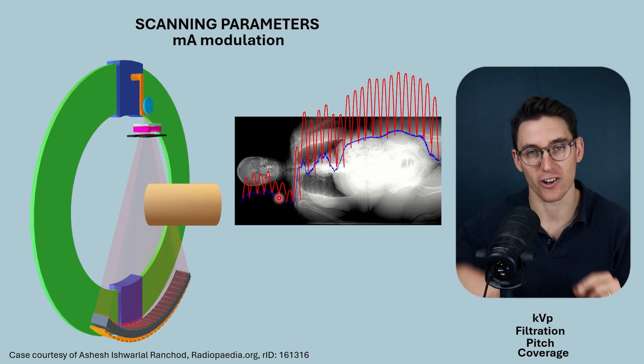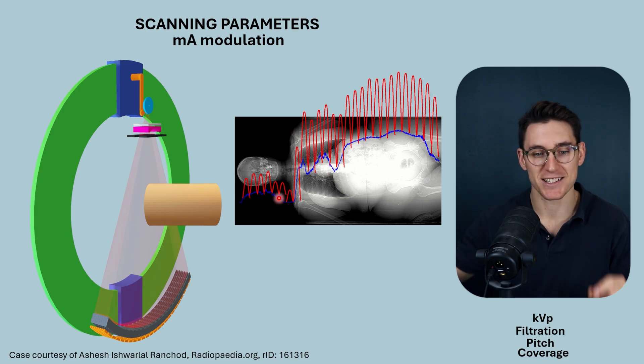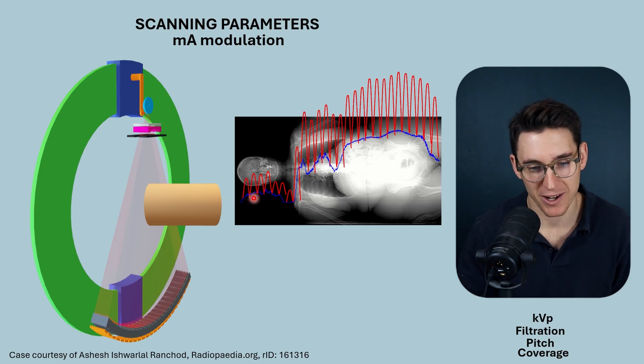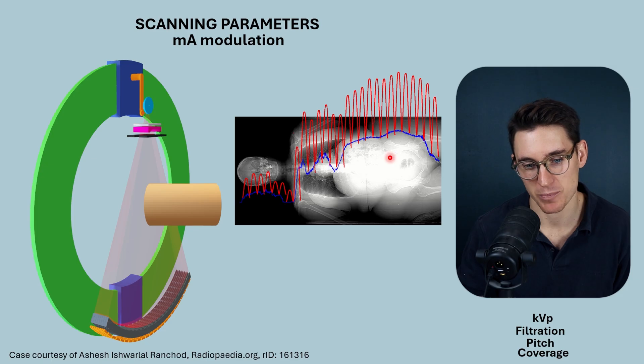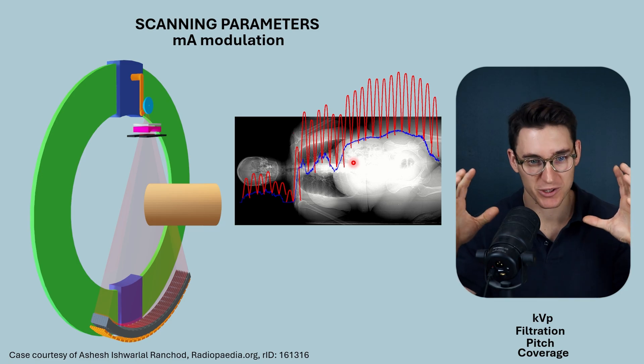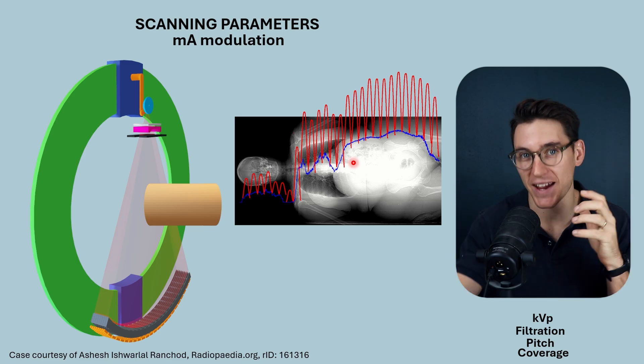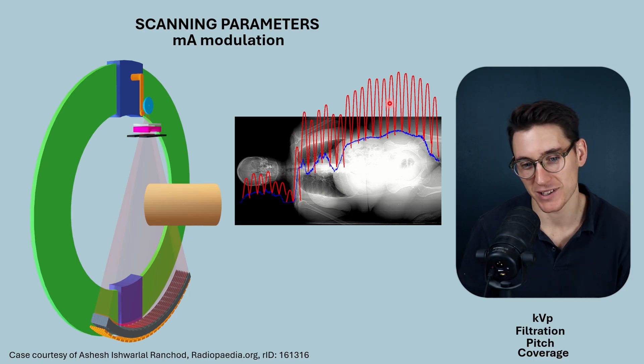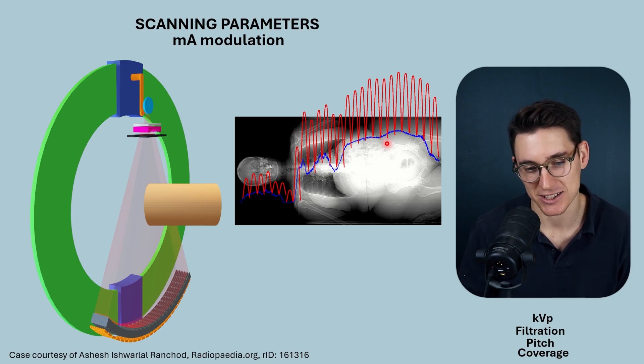We can combine these two factors — angular modulation and z-axis modulation — to get our overall current modulation for a specific patient. Notice how we still get that oscillating sine wave based on the dimensions of the patient, but the baseline current changes based on the density in the z-axis. This is perhaps the most difficult physics concept in the factors that influence dose, so I'd encourage you to spend time understanding the difference between angular modulation and z-axis modulation.